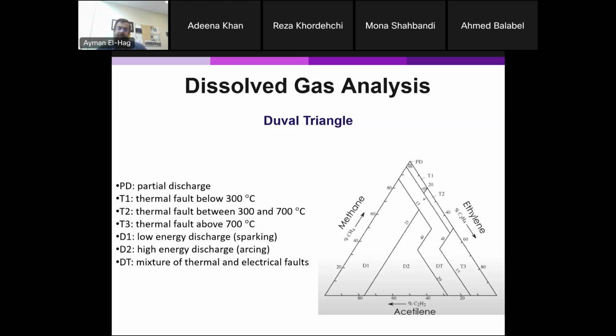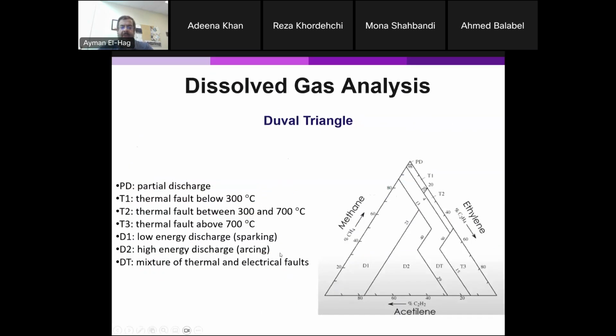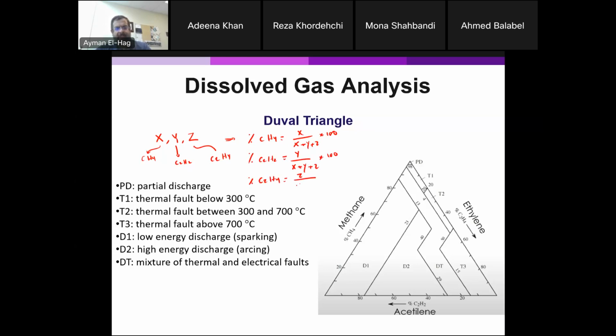Okay, and basically you try to see their values. So basically you find, for example, X, Y, and Z. This is how much ppm is your CH4, this is your C2H2, and this is your C2H4. So you find the X, Y, and Z, and then you find the percentage of, let's say, CH4 by having X divided by X plus Y plus Z times 100. You find the percentage of your C2H2, same thing, which is equal to Y divided by X plus Y plus Z times 100. And finally, the percentage of C2H4, which is equal to Z divided by X plus Y plus Z times 100.